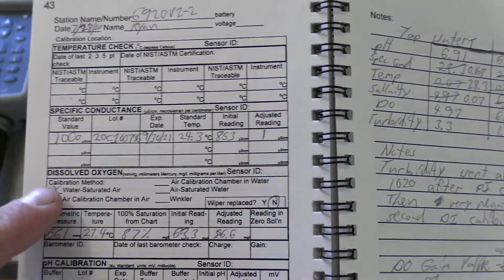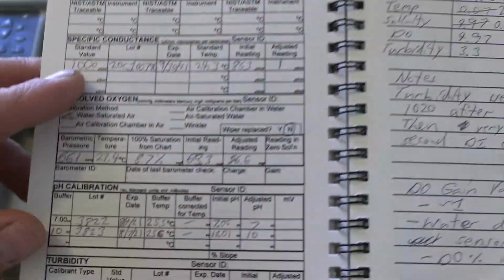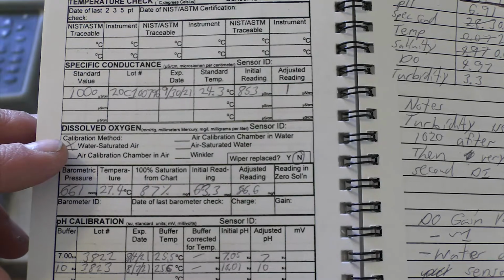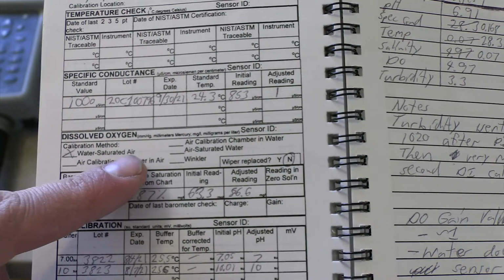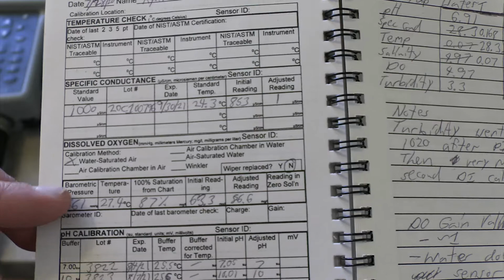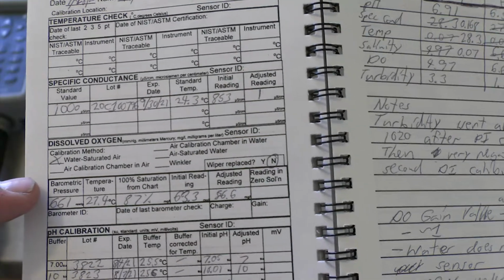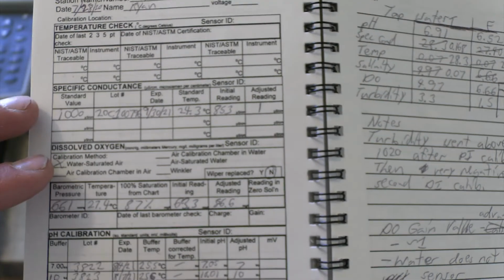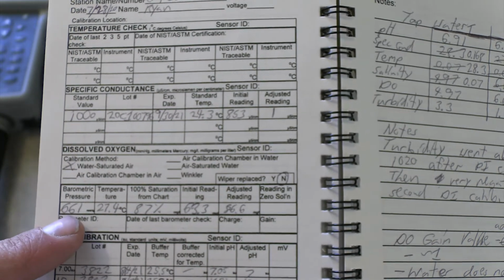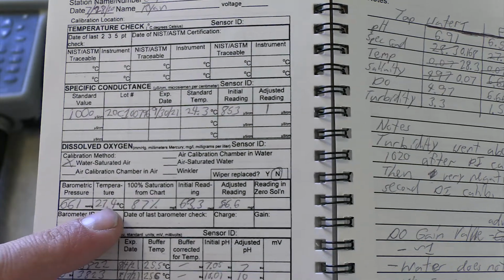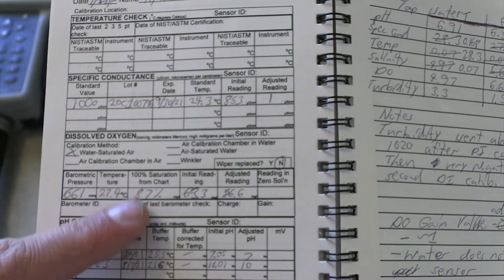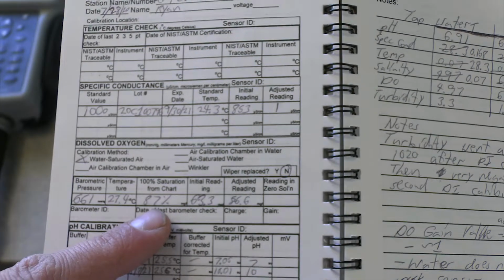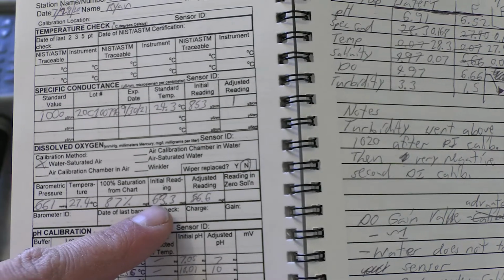And yeah, so that's great. You can put in other information, sensor ID, but it's not super important for the weekly. Okay, and then below that, we go to dissolved oxygen, and we calibrate with water saturated air, which is very simple actually. It basically includes putting about an inch or two of water in the bottom of the cup without the water actually touching the sensor. Then what we'll do is record the barometric pressure, the temperature, and then 100% saturation from the chart, which is actually 87%, and then the initial reading.